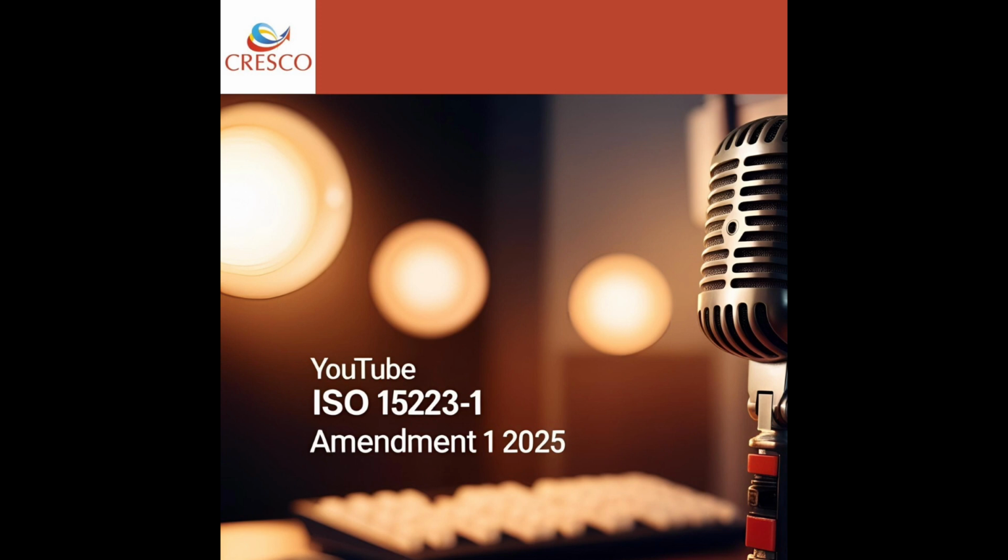So can you paint a picture for us? What might this actually look like on a device label we pick up? Sure. Annex A in the standard gives some good examples. You might just see the generic format, XXREP, and then the name and address right beside it. Or you could see specific country codes used. Things like CHREP for Switzerland, maybe EUREP still if it covers the whole EU, or even NZREP for New Zealand. And you mentioned NZLREP too, so sometimes three letters? Yes, it shows that flexibility, using two or three letters where they're accepted locally. Like NZL is also for New Zealand in ISO 3166-1.